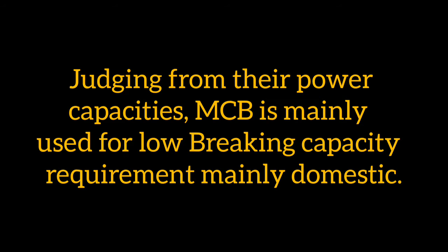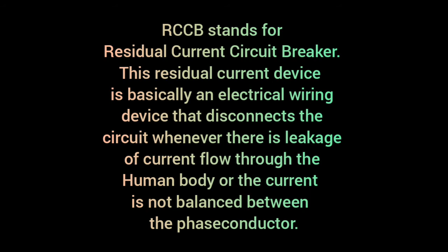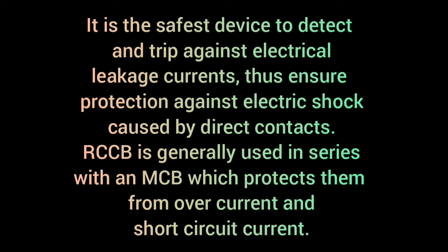Till now we have talked about MCB and MCCB and the differences between them. So now let's talk about RCCB. RCCB stands for residual current circuit breaker. This residual current device is basically an electrical wiring device that disconnects the circuit whenever there is leakage of current flowing through the human body or the current is not balanced between the phase conductors. It is the safest device to detect and trip against electrical leakage current, thus ensuring protection against electric shock caused by direct contact. RCCB is generally used in series with an MCB, which protects against overcurrent and short circuit current. Both phase and neutral wires are connected through RCCB devices.